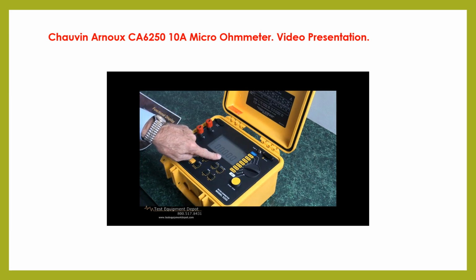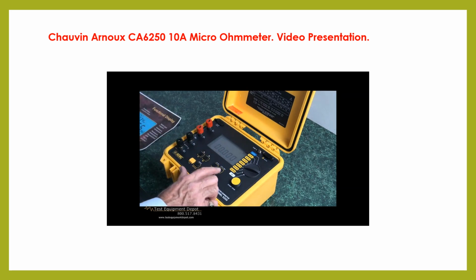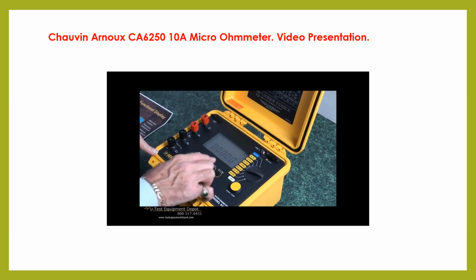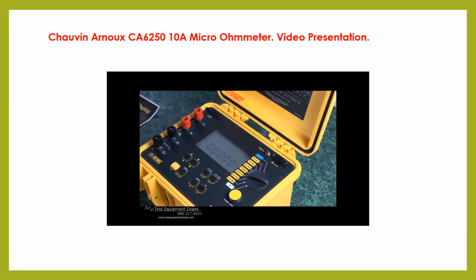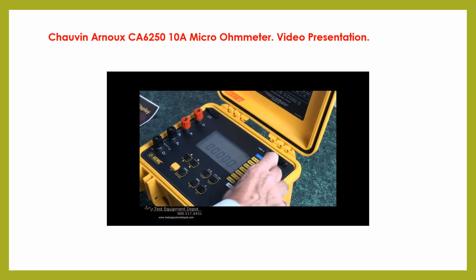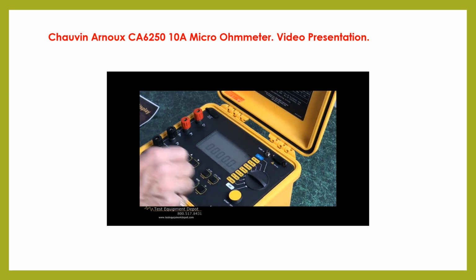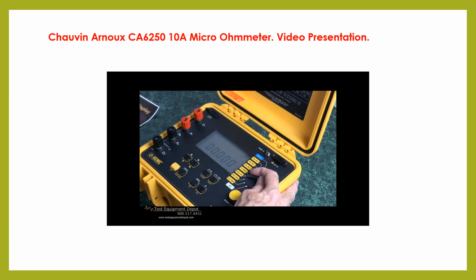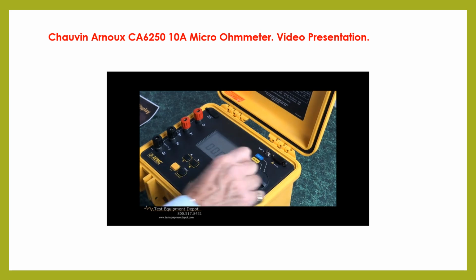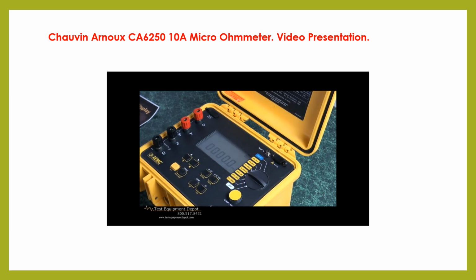This tells us we are in the resistive mode, but I can toggle that back and forth into the inductive mode, or I can go to the auto mode. Okay. This is where I'll be moving it from test to test. And we'll notice that we get more decimal points the further up we go, the more sensitive we get. Okay. And it'll automatically change from ohms, in this case, to milliohms. So we'll get automatic adjustment of the range.